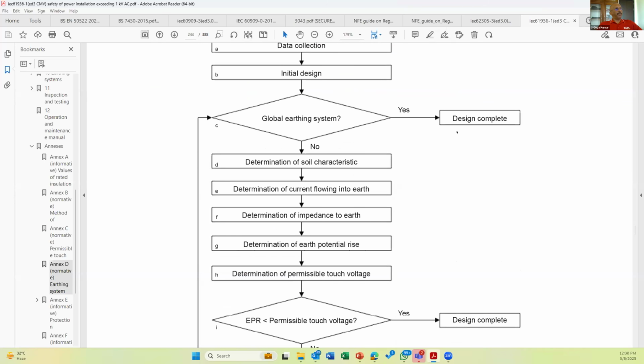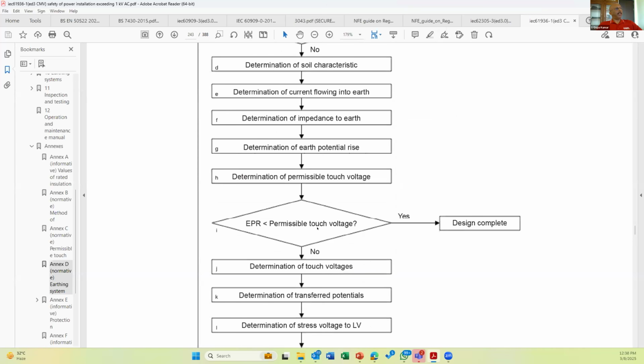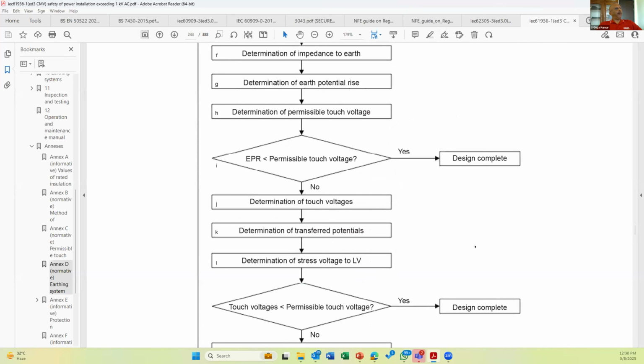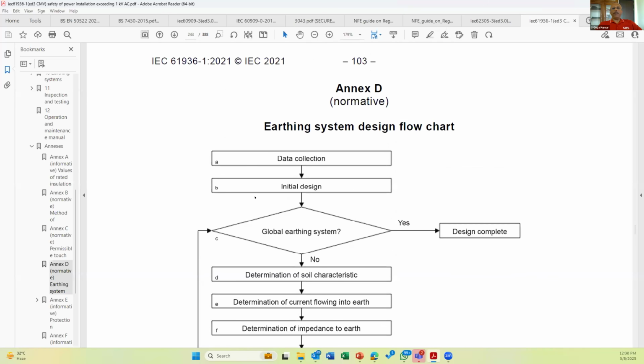If you cannot make a global earthing system, that means you have a standalone substation, which may be part of a transmission substation or a distribution substation. Under that condition, we have to determine the soil characteristics, the current flowing to earth, meaning the earth electrode current IE, the earth electrode resistance RE, how much GPR is created, and whether the permissible touch voltage is greater than the touch voltage. Compare the EPR and the permissible touch voltage. If yes, design complete. Or you have to follow this particular method and make grading rings so that the earth potential rise and the step and touch voltages are within the tolerable limits. So this is the method. For industrial and commercial premises, the best way is to go for a global earthing system. I hope I answered your question.